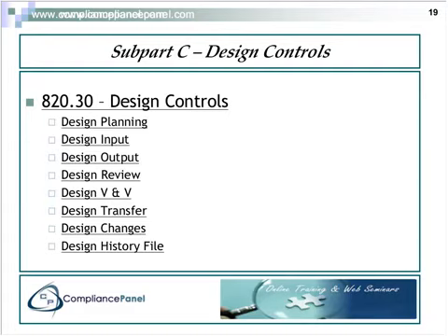And records is a big, important part of this, being compliant with this. So these procedures should be brought to your attention by your supervisor or through additional training modules within your organization. And design controls here starts with the conceptual part of design, which is design planning, all the way out to design history file, design changes, etc. So there needs to be controls in place for the whole design process.